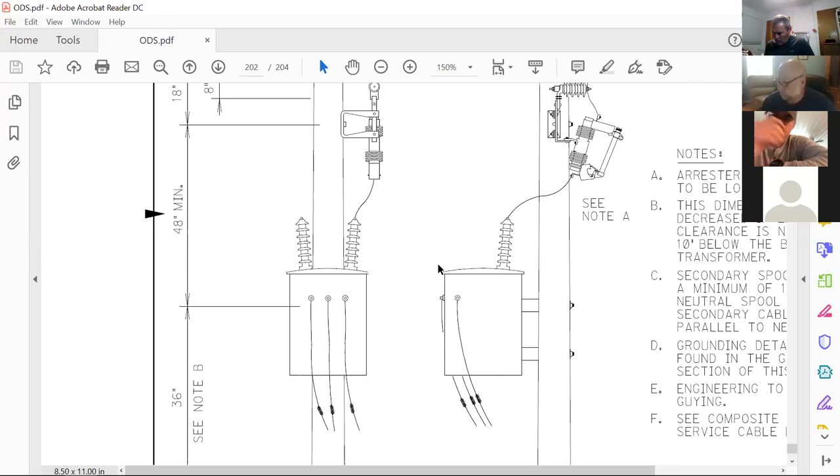No, hold on. If you figure 37.5, if the transformer here will go to 150%, and it's inherent, you don't have to change anything. You don't have to move any switches. You don't have to do anything different. It's inherent to all manufactured transformers that they will go to 150% for a short-term period. Do I need to do the same thing with the fuse? No. Hold on. So if this goes to 37.5, my 5 is still good protection.